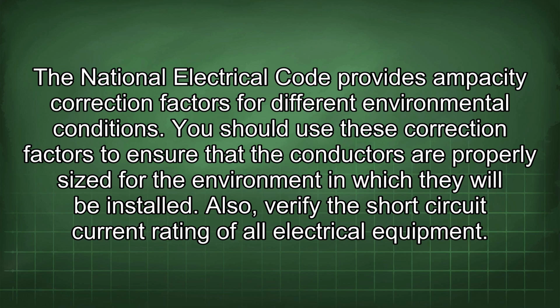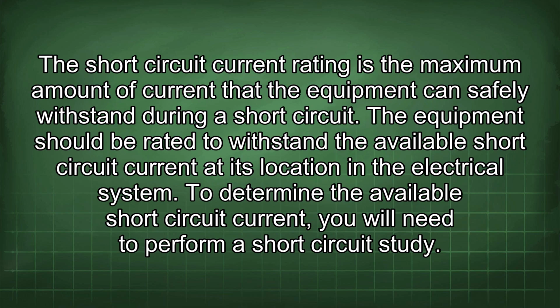Also, verify the short circuit current rating of all electrical equipment. The short circuit current rating is the maximum amount of current that the equipment can safely withstand during a short circuit. The equipment should be rated to withstand the available short circuit current at its location in the electrical system.